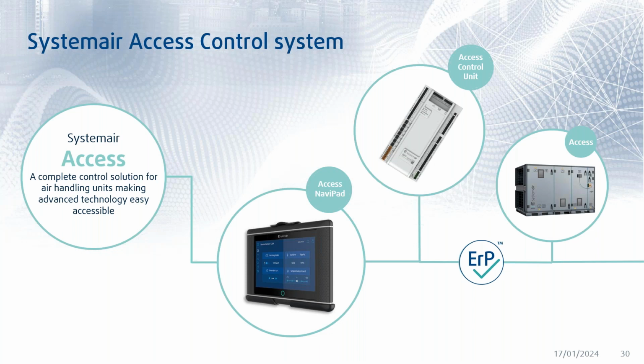It's no longer good enough to just have an analog system where you would send a signal to your actual component. So you're sending a 5-volt signal and you're hoping that you're actually getting that 5 volts running on the fan. What we use is a Modbus system internally within the actual unit itself. So communication is two-way. So not only are you sending the information to the component, to the fan, or to the damper, etc., you're getting that information back as well. So when it comes to energy modeling, you'll be able to get the actual working points and the energy consumption of that specific component within the unit.